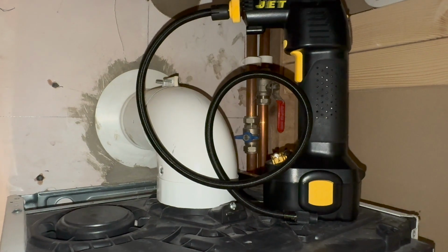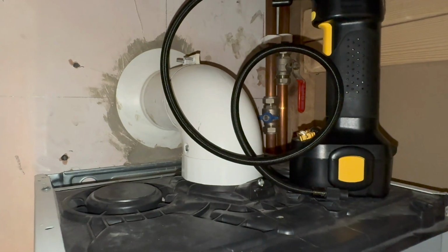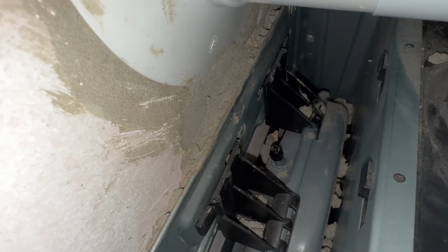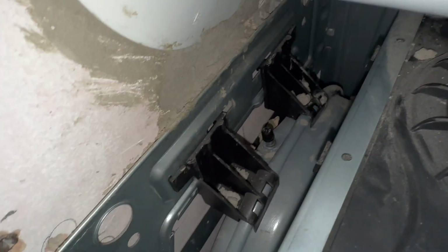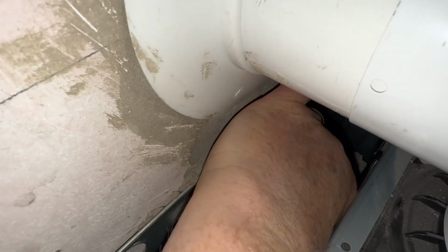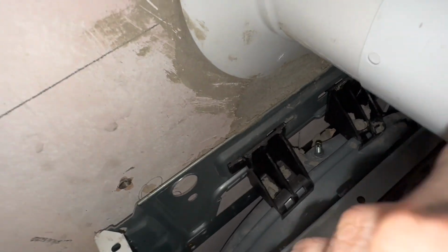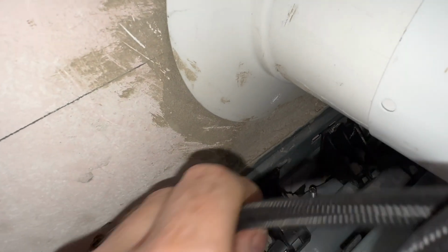Now that's clean, we can get it back in. Now checking this expansion vessel on this boiler is a proper faff, because it's actually behind there, so you can just see the Schrader valve there. So basically what I'm going to do is get my hand in to take out that, and then my little pump I've got to try and find to get it in. Don't help, it's in a cupboard as well.